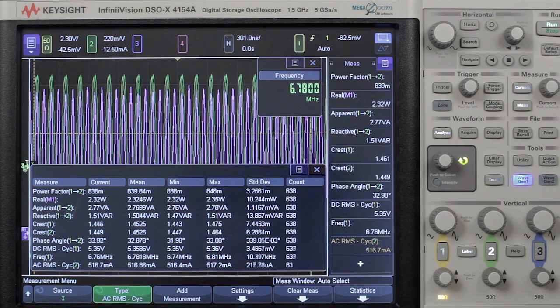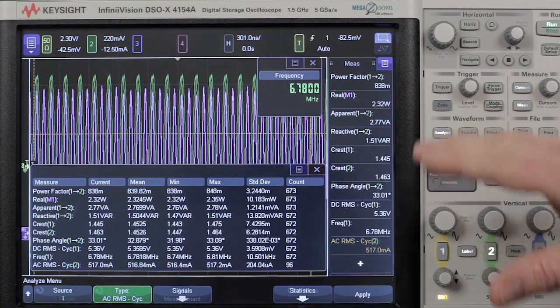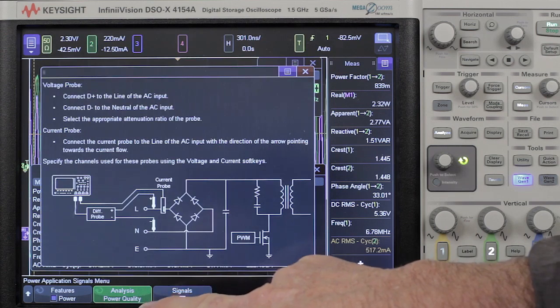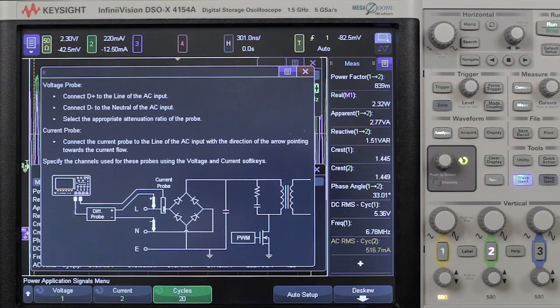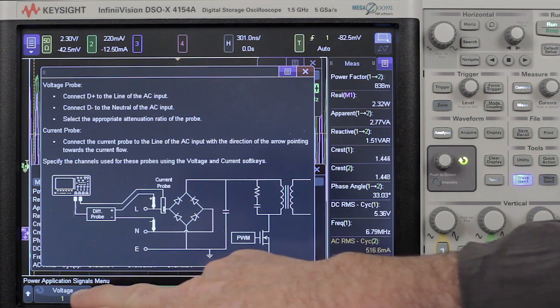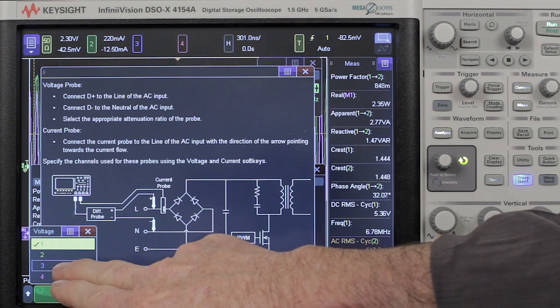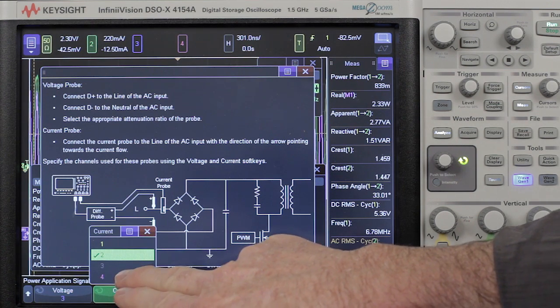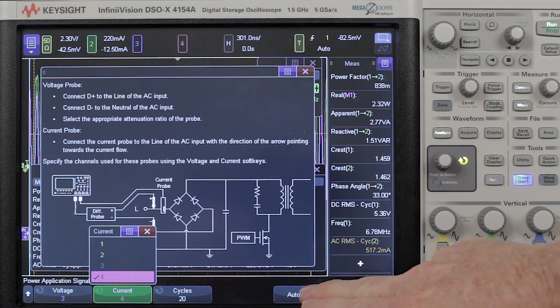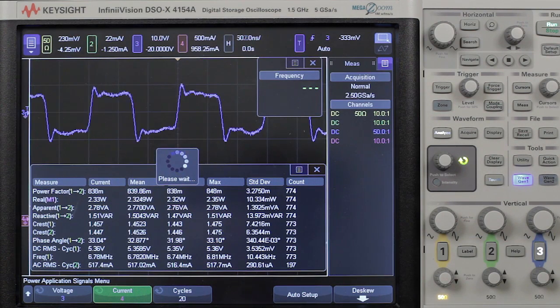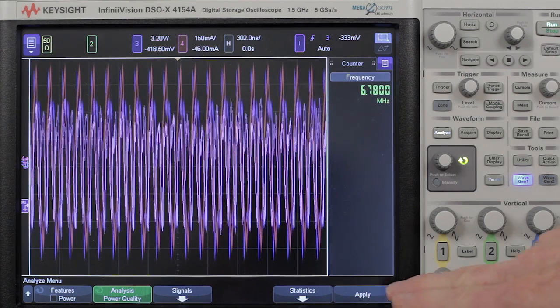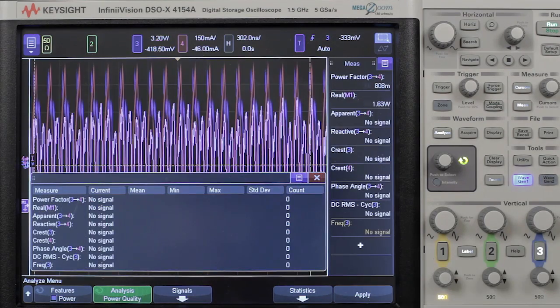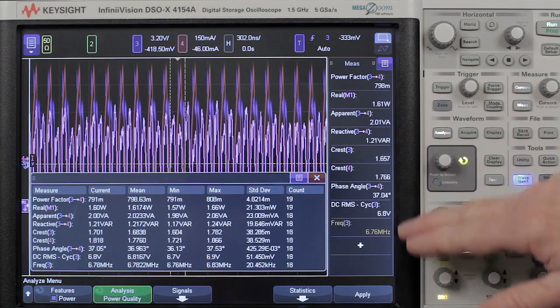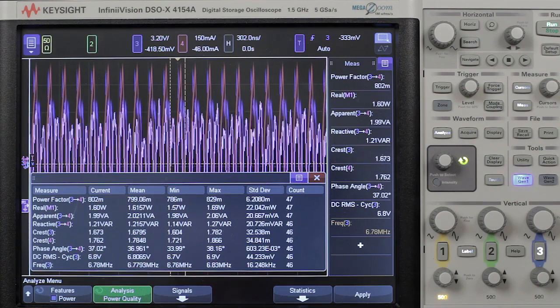Now if we want to perform the same measurement on the PRU, again we can go back into that menu, and in this case I have my channel 3 and channel 4 connected up to the PRU. Select 3 for voltage, 4 for current, auto setup. Then apply, and there we have the power on the PRU.